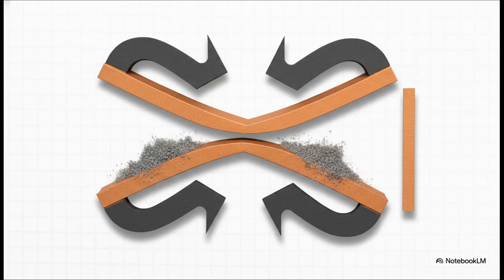Finally, our sources really hammer home the importance of practical headroom and mechanical stability. Mechanical stability is inherently linked to electrical safety. Just think about it. A short circuit event generates these massive electromagnetic forces that will physically bend and deflect your conductors. If a short circuit bends your bus bar, your perfectly calculated 8 millimeter clearance, it's gone. It completely vanishes in a millisecond. Like the Copper for Bus Bars guide points out, having greater section stiffness reduces that deflection. You also have to think about everyday realities, like how dust settles way faster on flat horizontal surfaces than on vertical edges, which slowly ruins your creepage path over time. Oh, and last-minute hardware changes on the factory floor? They will always erode your electrical margins.